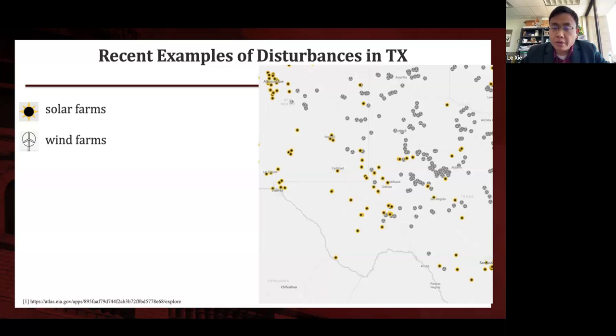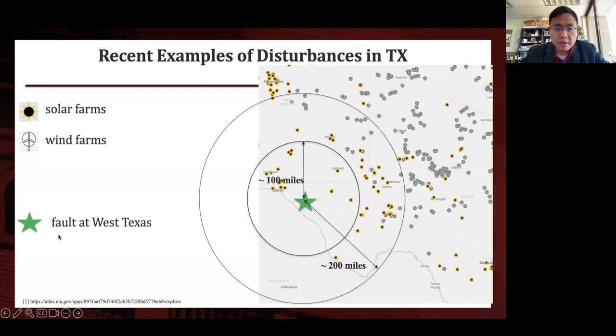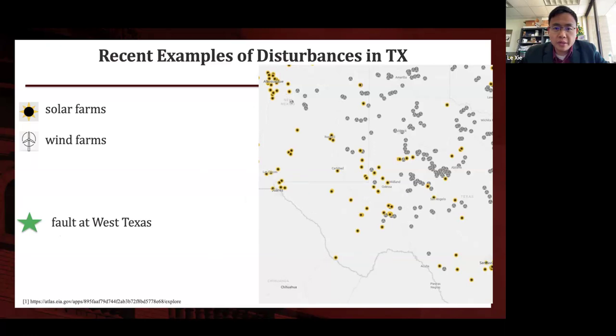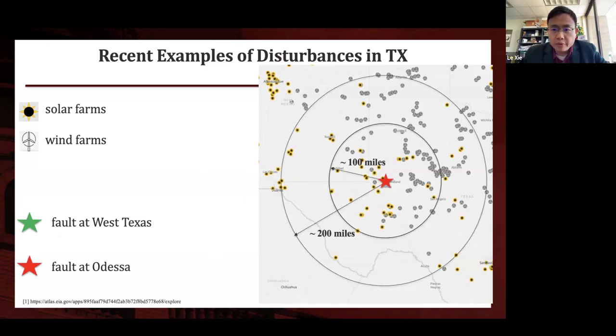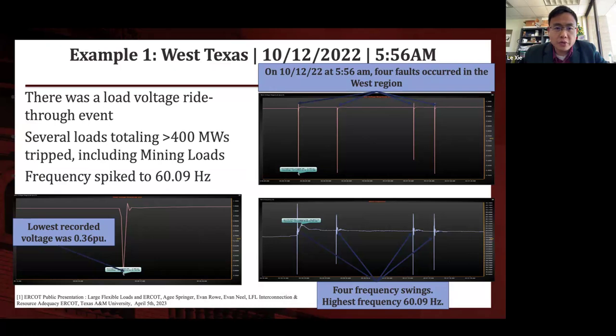The same thing is happening now in the computing side, which is very new. There was a recent event in West Texas where a disturbance created a fault, then recorded a low voltage ride-through that caused not only failure of solar farms, but also the tripping of large mining loads.